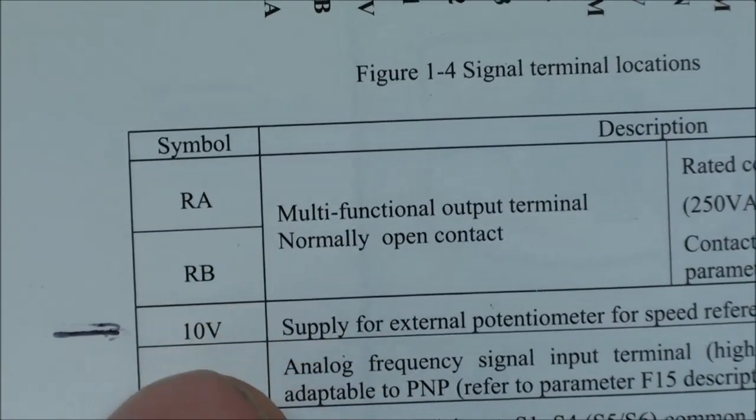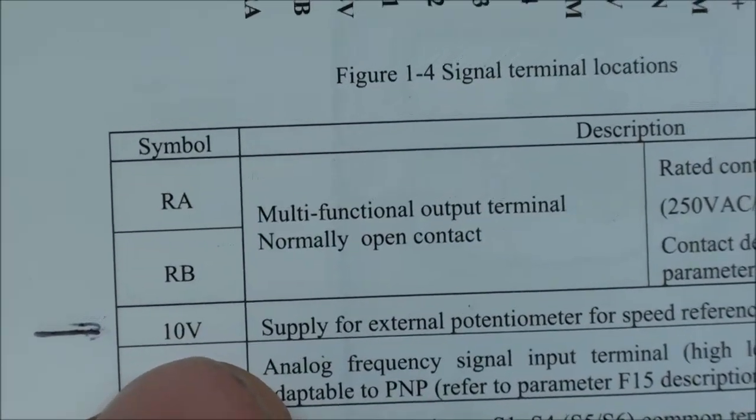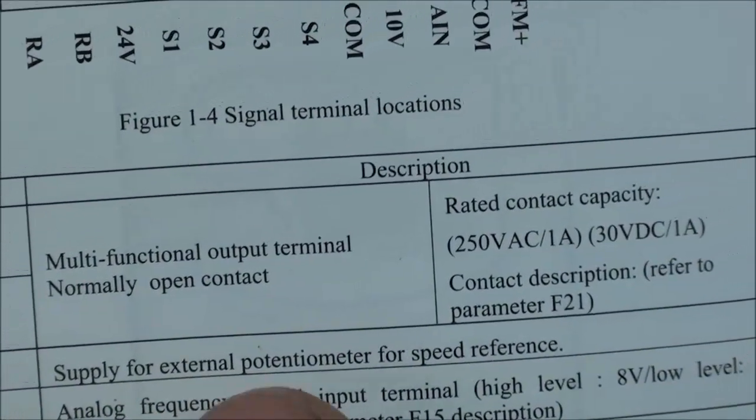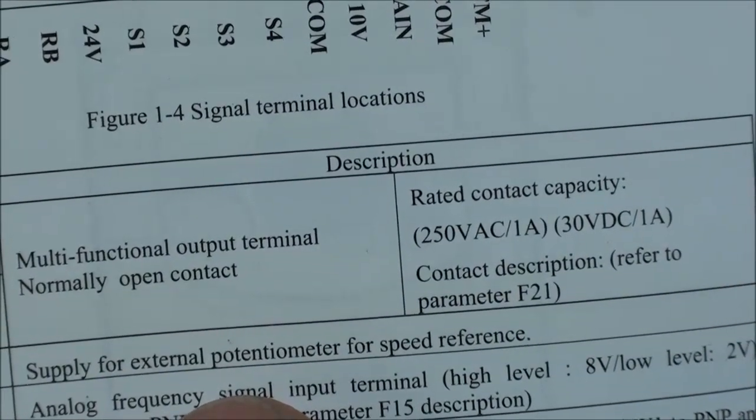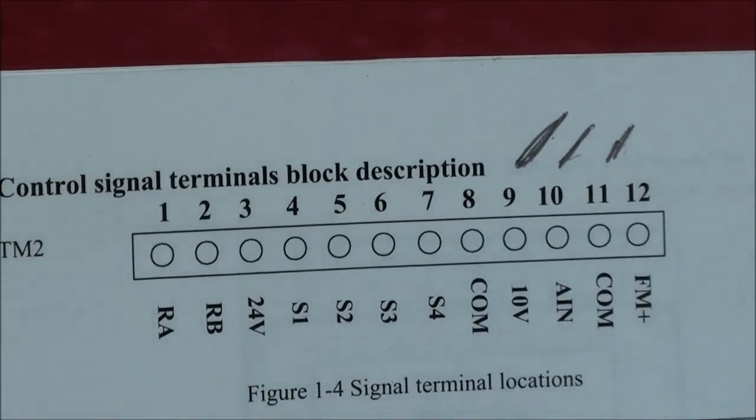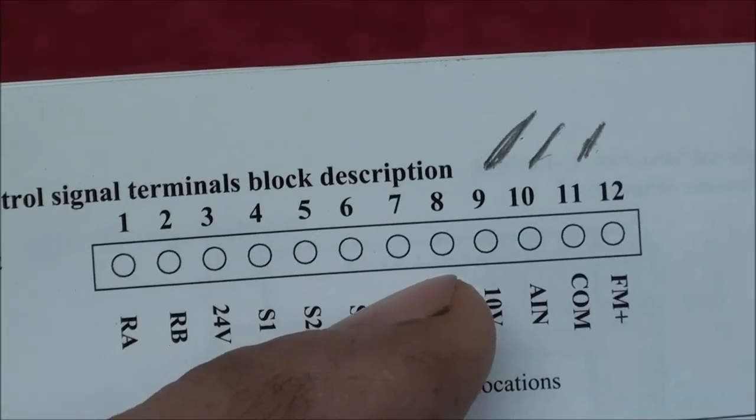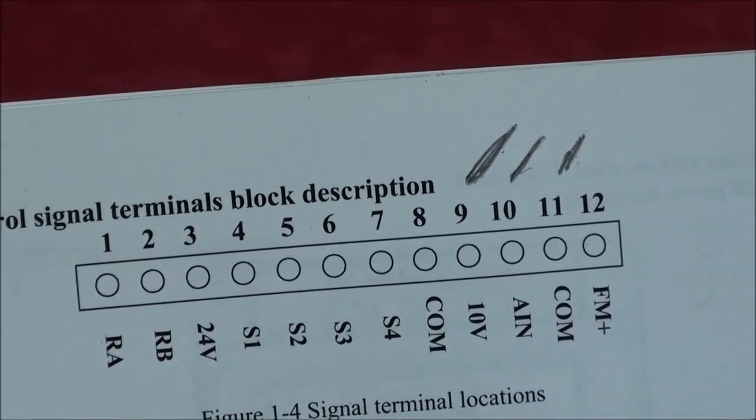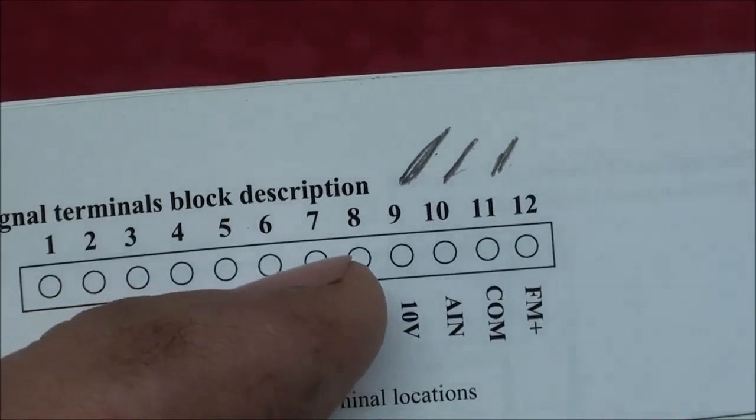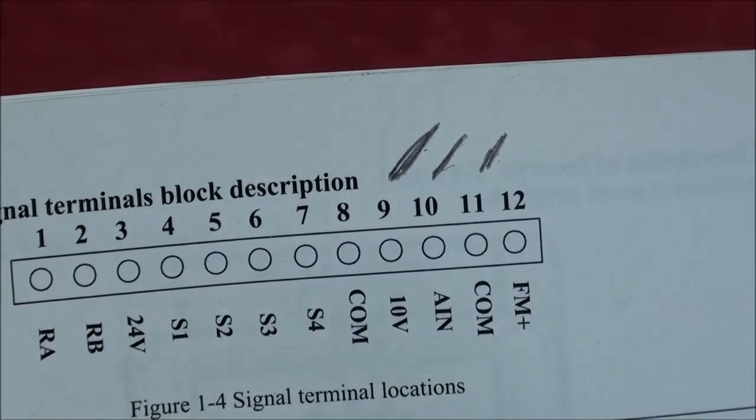But here it tells that the terminal 10V is the supply for the external potentiometer for speed reference, and on the top here that's the terminal block that is on the bottom of the VFD, and I'm going to use terminals 9, 10, and 11.